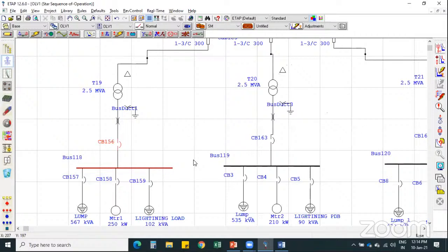Now, certain ground fault protections exist in the system, that is REF protection, restricted earth fault protection, and standby earth fault protection. As one of our attendees mentioned earth fault protection, I will also mention that there are certain other protections for earth fault, that is REF and SEF protection. REF means restricted earth fault protection, which is used for unit protection of a transformer. And SEF means standby earth fault protection, which is the very last line of defense for earth fault protection. If any protective relay in between the path fails to operate, then at last the standby earth fault protection will operate, and it will protect the system from getting severely damaged.